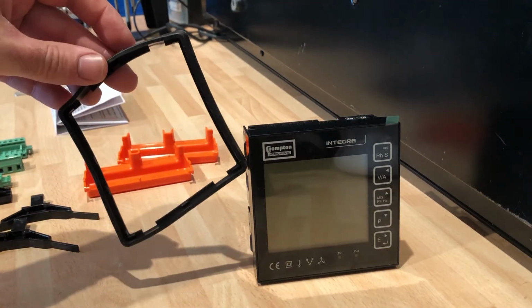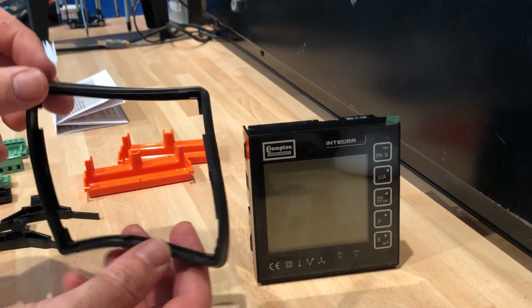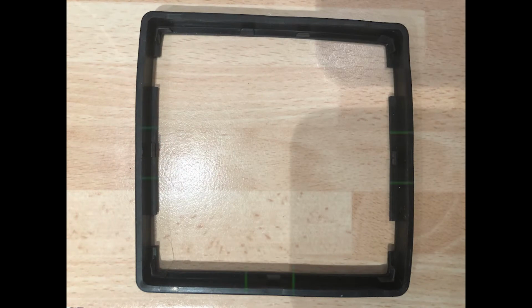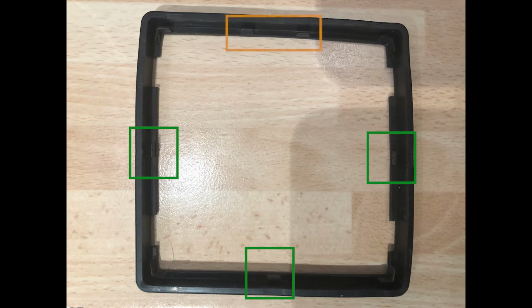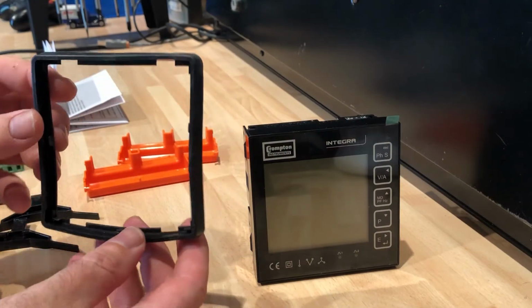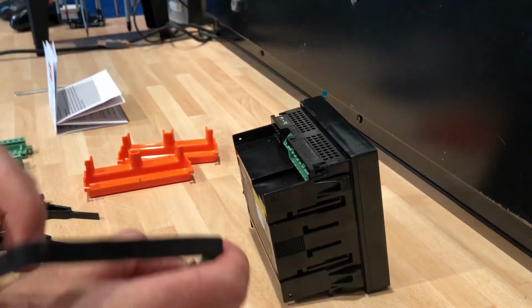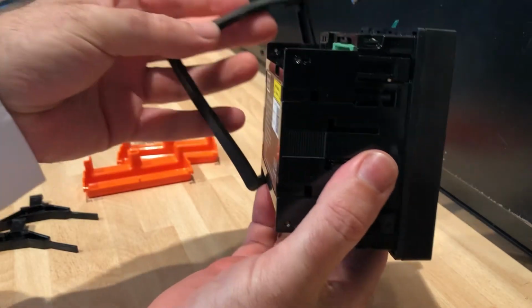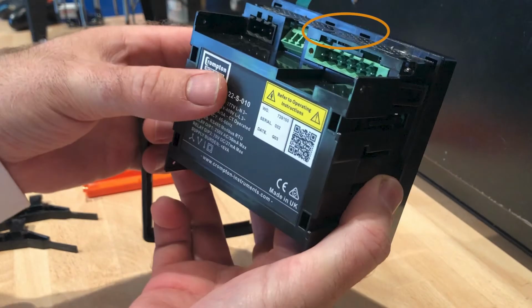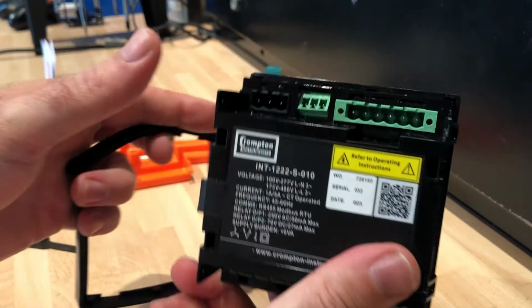Firstly, if you have the kit for IP65, you'll want to apply the panel gasket first. The panel gasket has 3 single pips on 3 sides, but on one side it has 2 pips to identify the place of installation on the product. If you look at the product and find the top, there are 2 holes for the 2 pips of the panel gasket, which identifies the orientation of the gasket.